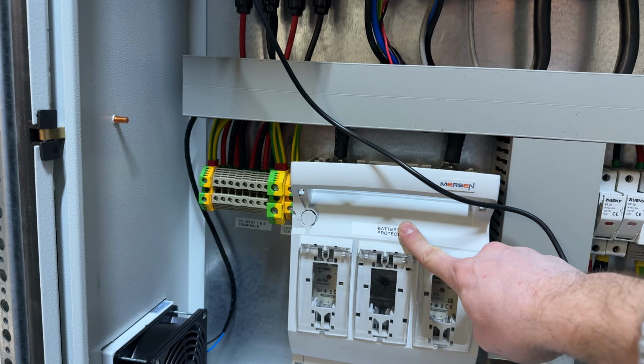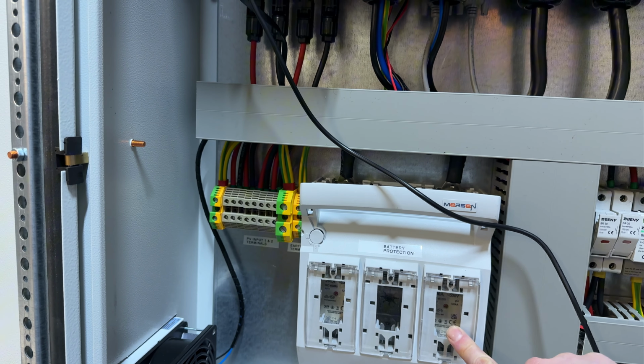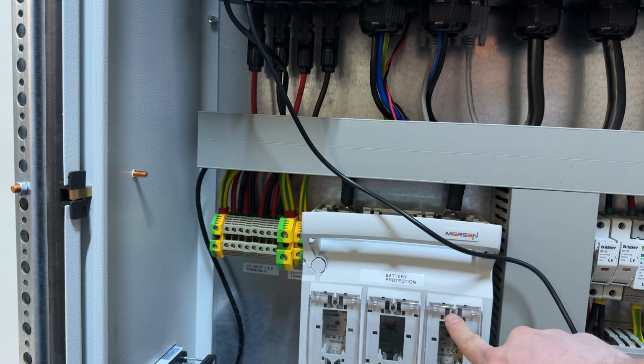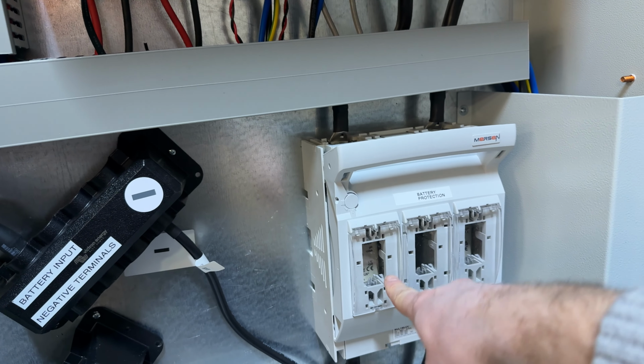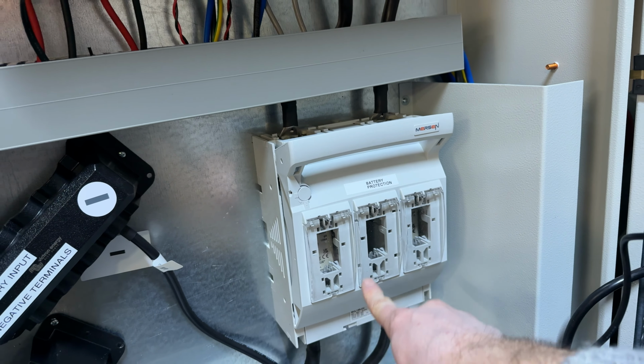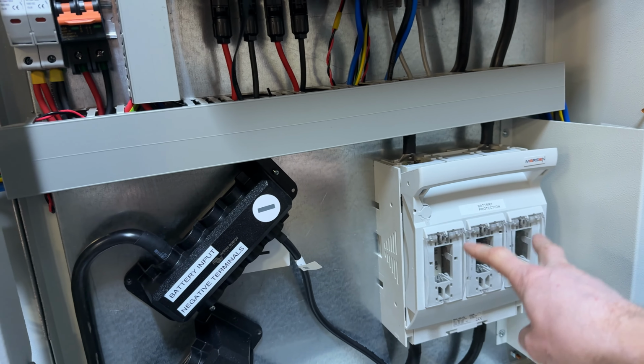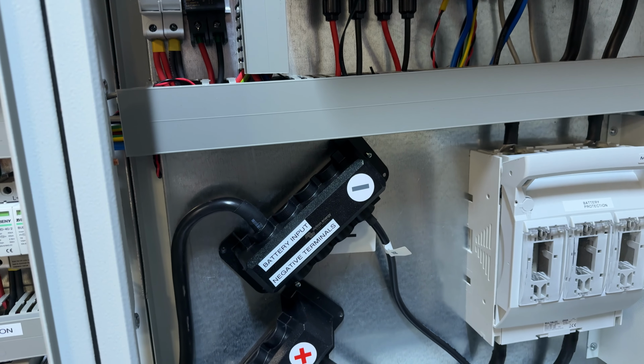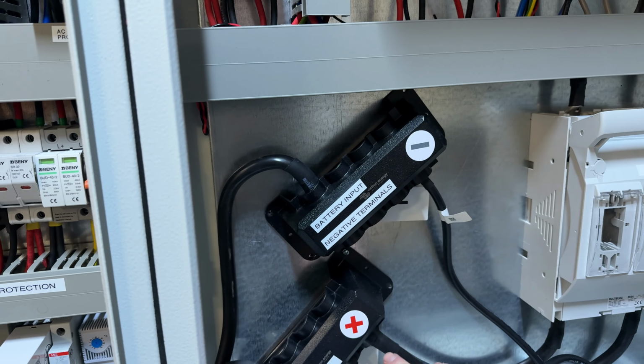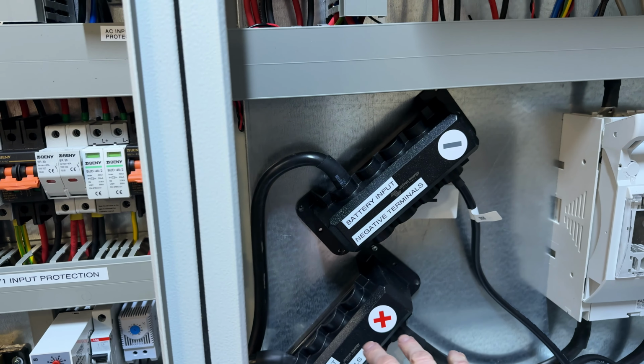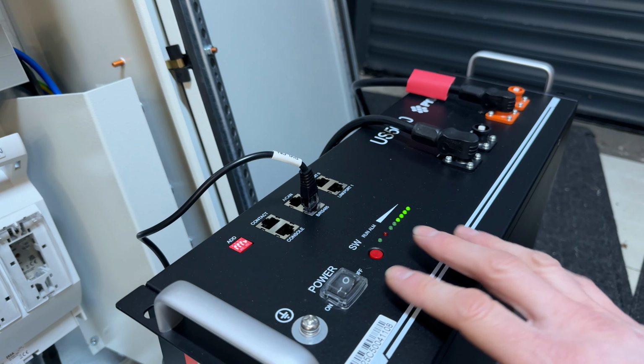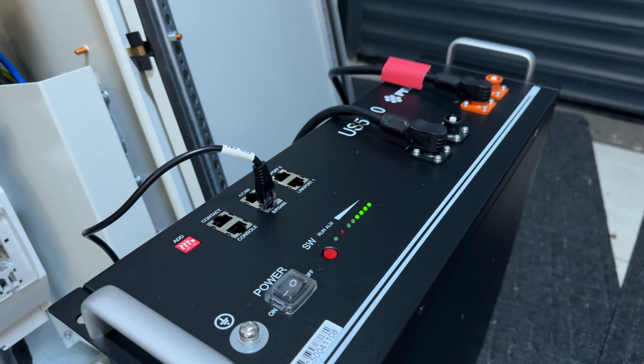Now let's start from this side. This is the fuse connection from the inverter to the batteries. And there is another one from the inverter to the batteries with 200 amp fuses. Both DC links are connected together to a common bus bar. That's the negative and that's the positive. And from this bus bar, we feed the energy back to the lithium-ion batteries. In our case, we have just a single battery.